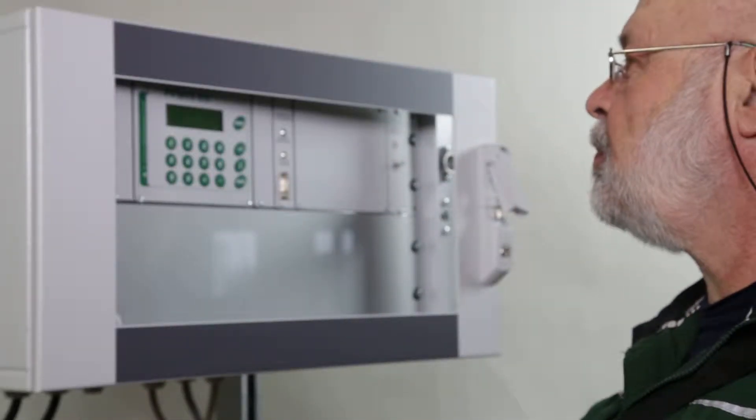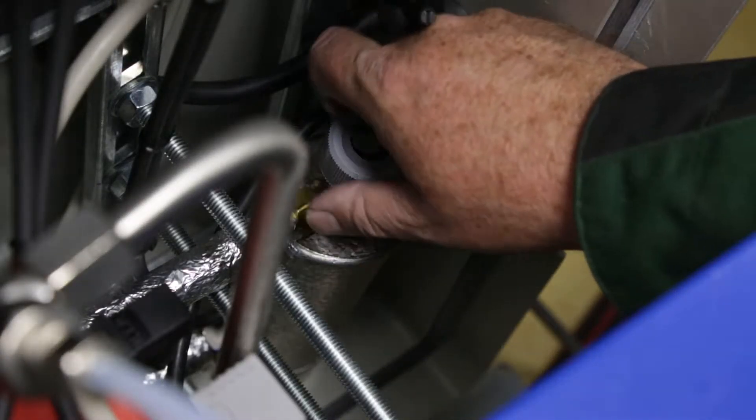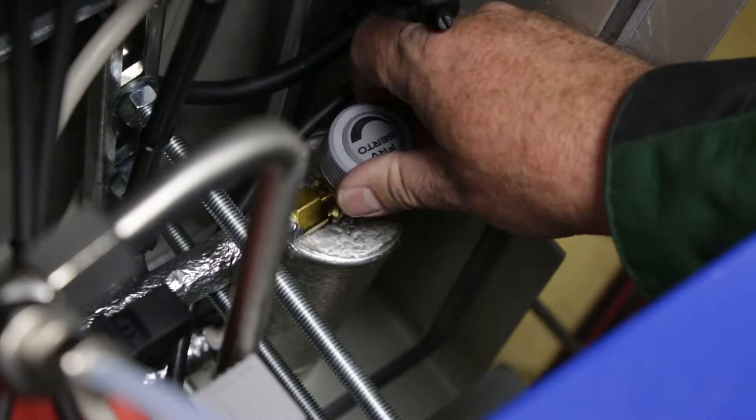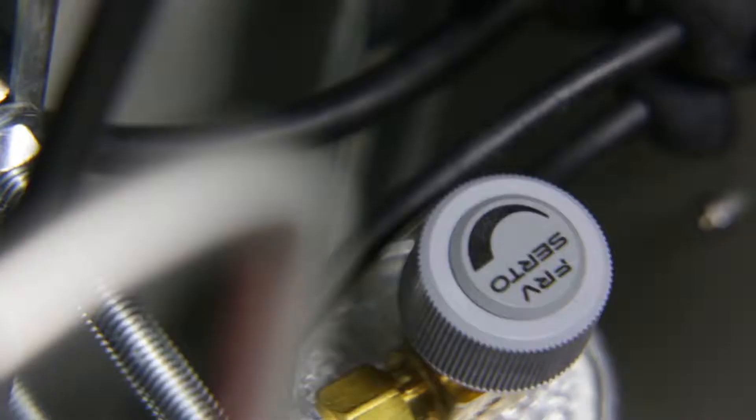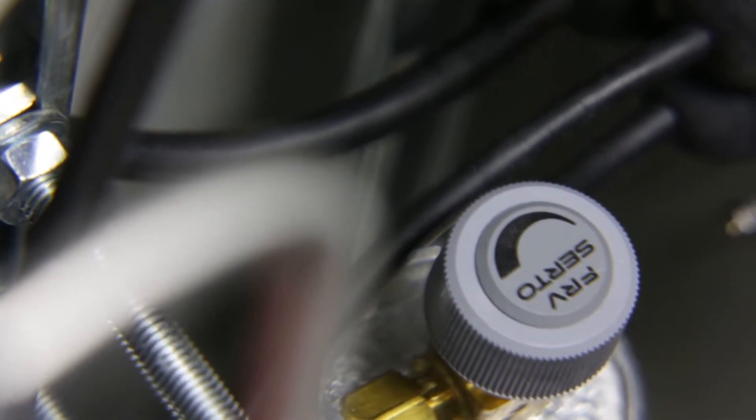Adjust the flow of the measuring cell. The corresponding valve is directly at the injector air blower. Adjust the flow for the desired dilution of the measuring gas between 30% and 70% at the dilution air valve in the probe unit.